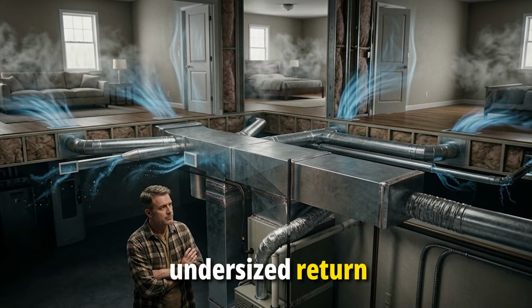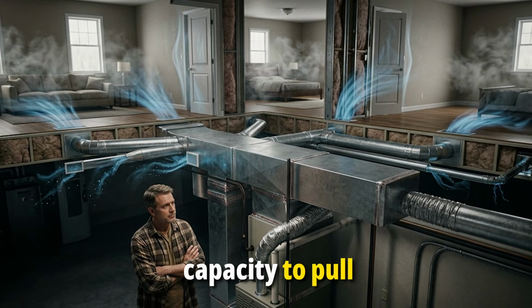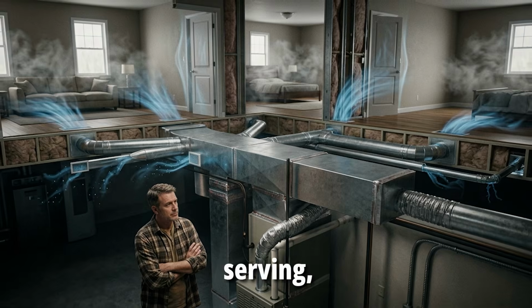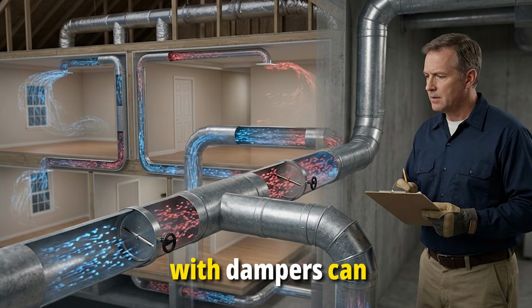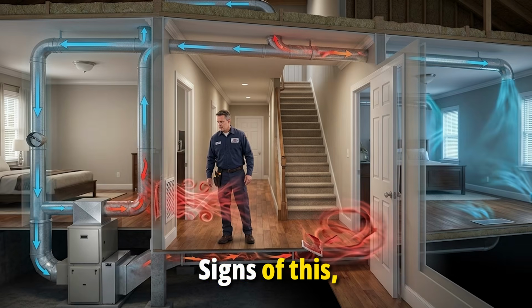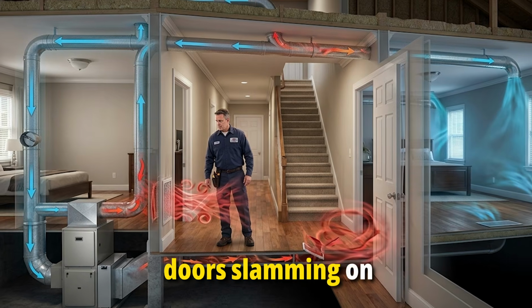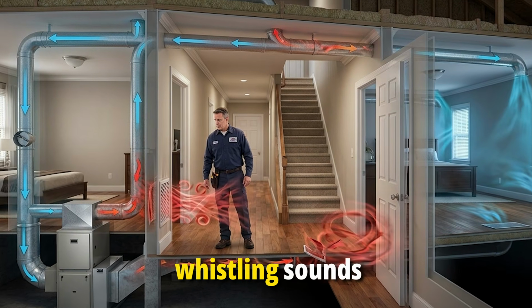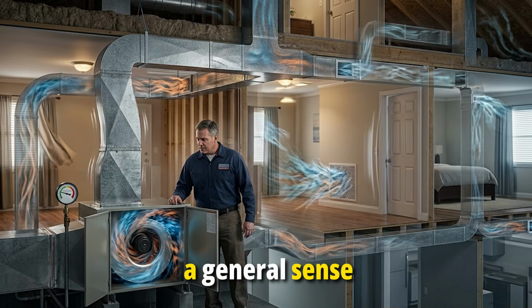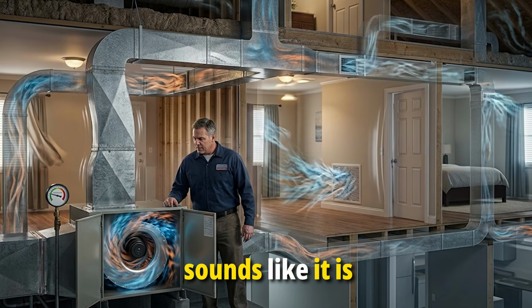And if your system has undersized return air, not enough capacity to pull air back from the rooms it is serving, restricting supply airflow with dampers can actually make that worse. Signs of this: doors slamming on their own when the system runs, whistling sounds at return grills, a general sense that the system sounds like it is straining.